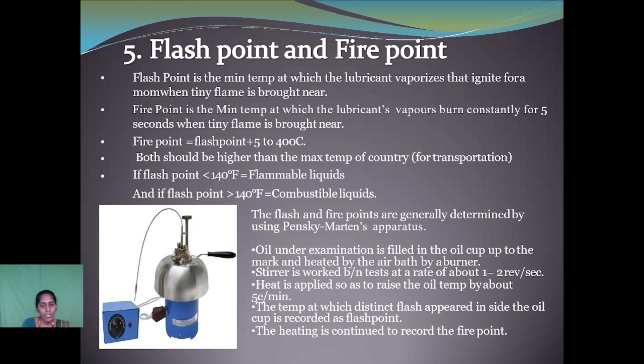Flash point less than 140 degrees Fahrenheit means flammable liquids. And if flash point is greater than 140 degrees Fahrenheit, it means combustible liquids. The flash and fire points are generally determined by using Pensky-Martens apparatus. Oil under examination is filled in the oil cup up to the mark and heated by an air bath with a burner. The stirrer is worked at a rate of about 1 to 2 revolutions per second. Heat is applied so as to raise the oil temperature by about 5 degrees Celsius per minute. The temperature at which a distinct flash appears inside the oil cup is recorded as the flash point. The heating is continued to record the fire point.